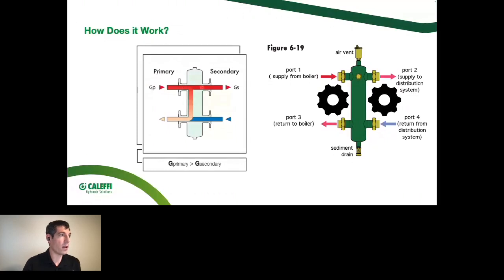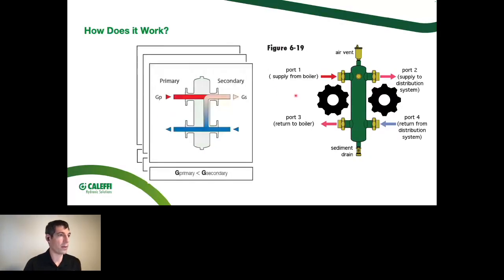So we're only really pulling off the 5 GPM that we need to keep this wheel spinning at the right speed. That's the simple magic of primary secondary piping: if there is an imbalance, we just have enough space for that flow rate to go back through this big, wide open vessel without a lot of pressure drop, and it keeps the customer on the left side of the equation happy.